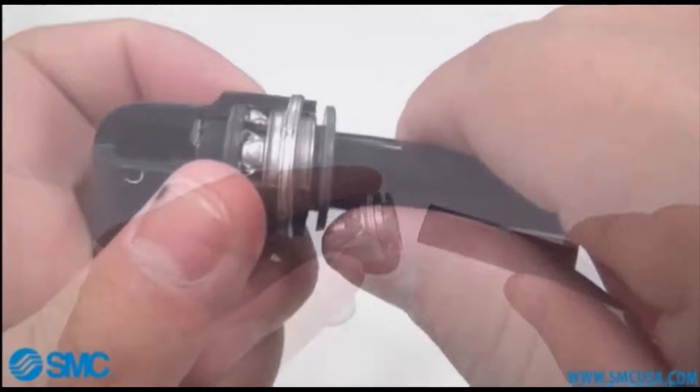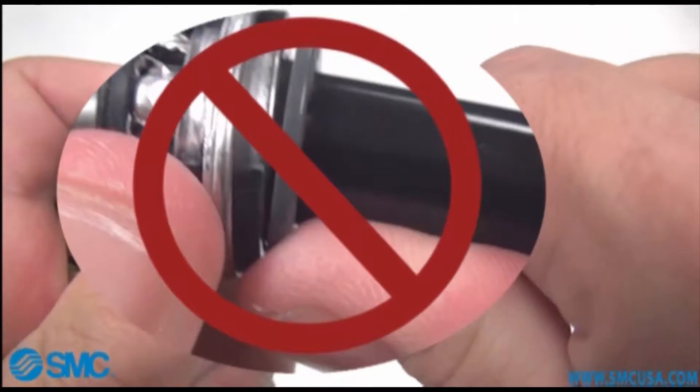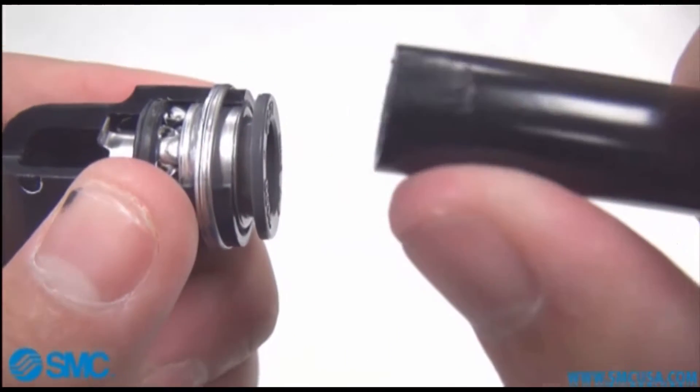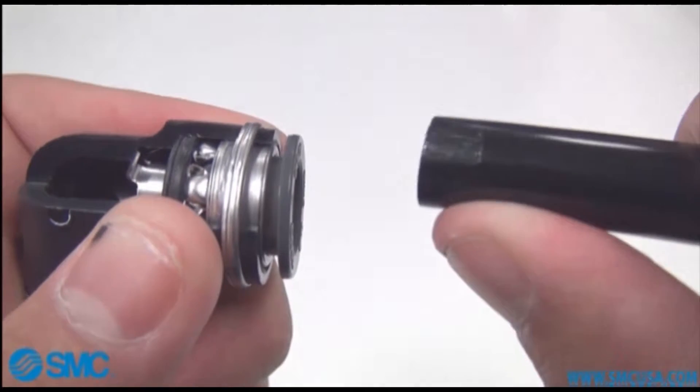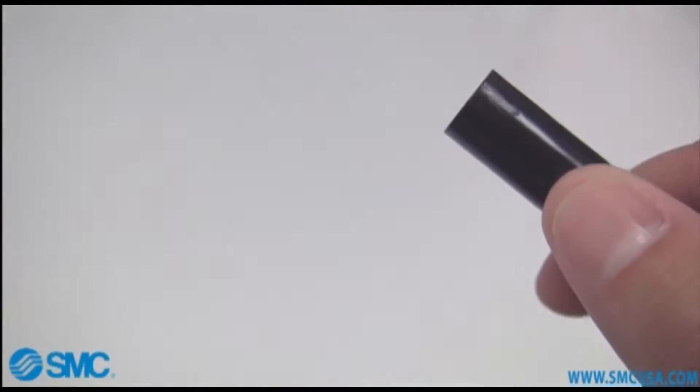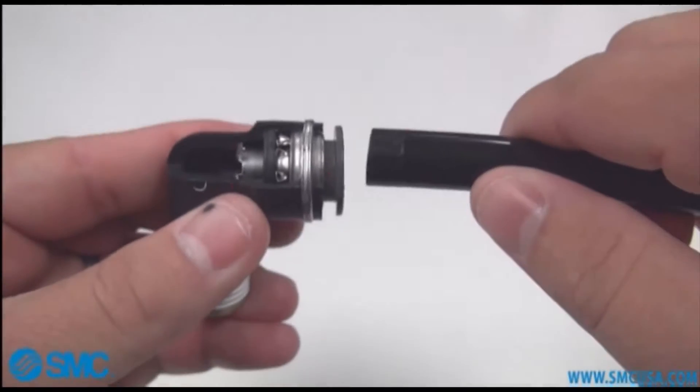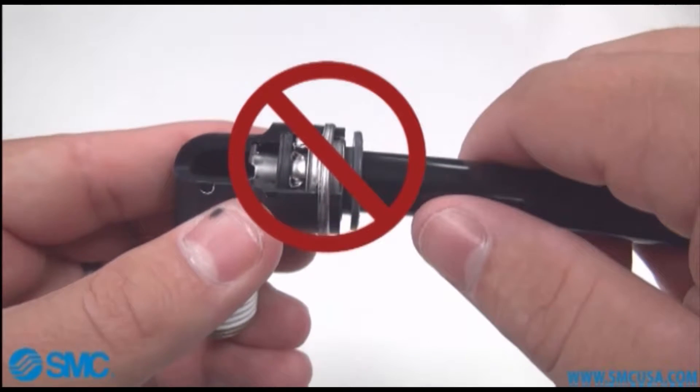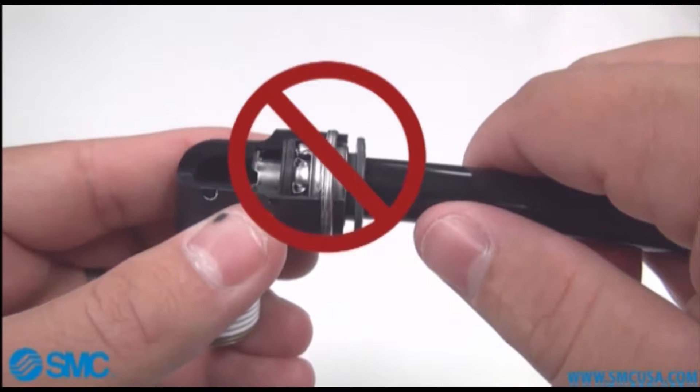An incorrect method of removing the tubing is pressing the button on one side. As you can see when you do this it will create deep scratches on the tube which could potentially create a leak path for air to escape. This would not be good to reinsert into the fitting and would have to be recut properly before reinserting it into the fitting.